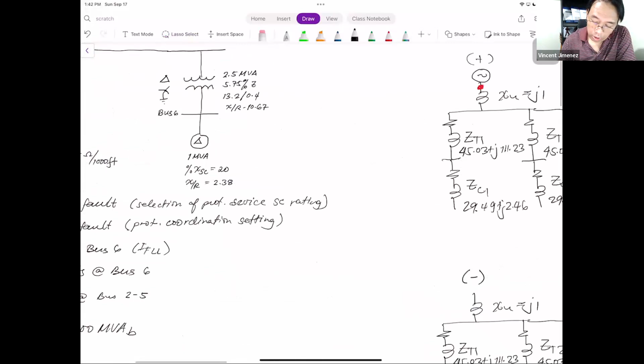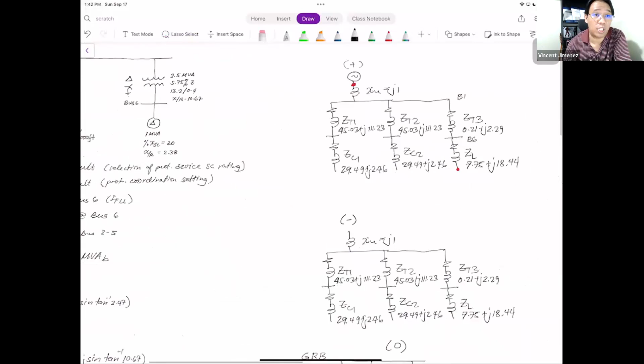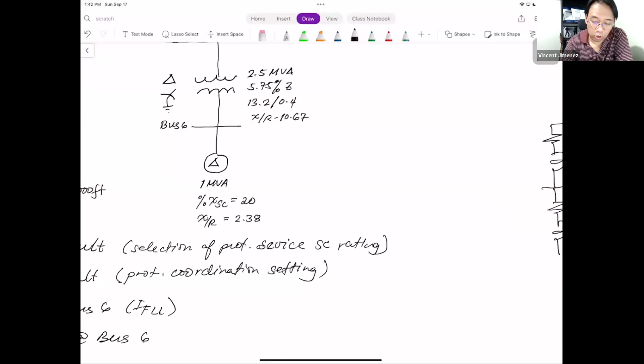So, objective number 4: line-to-ground fault at bus 6. What is a line-to-ground fault? When a ground fault occurs at bus 6, what would that line-to-ground value be? Using the 30-cycle computation, and since the motors at the LV side are delta-connected, they don't contribute to the ground fault — it can't flow through. So the only source would be your utility.